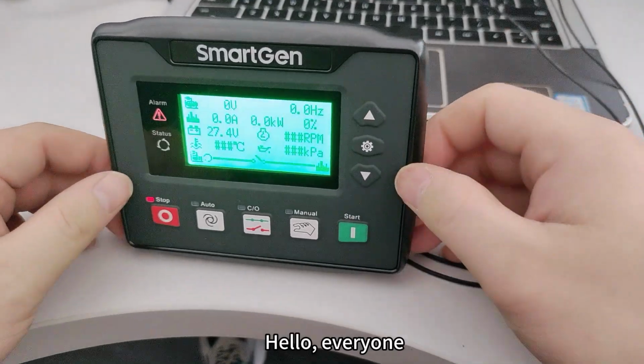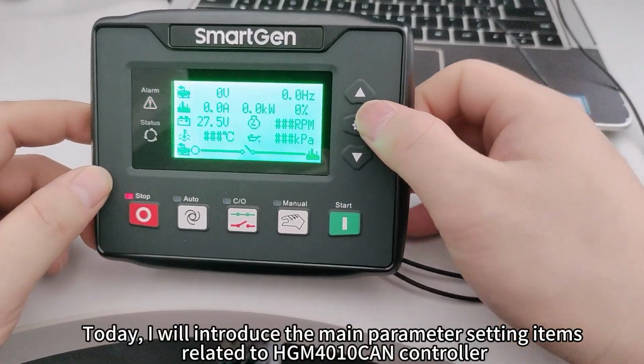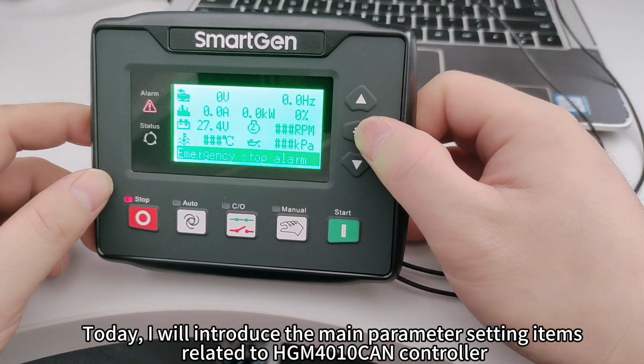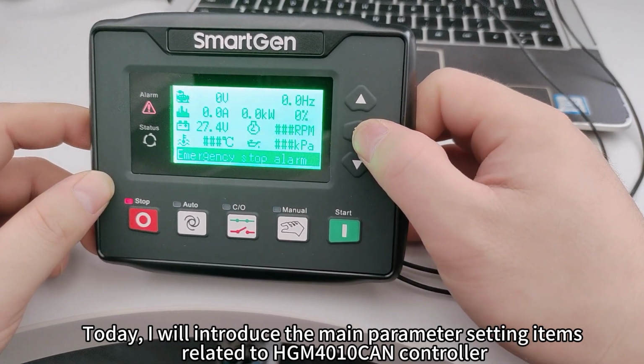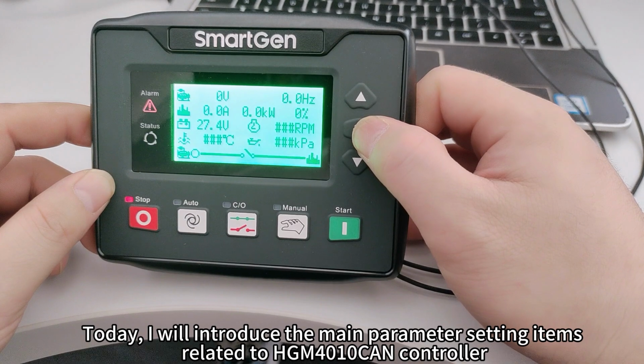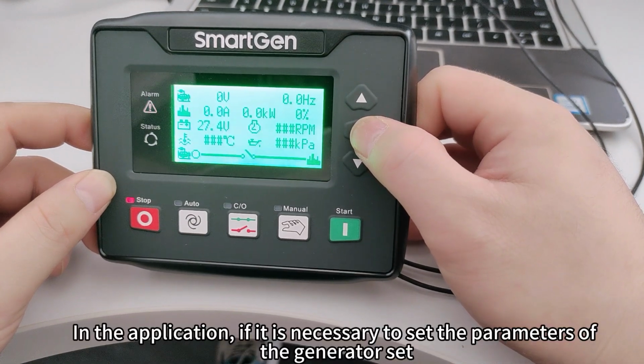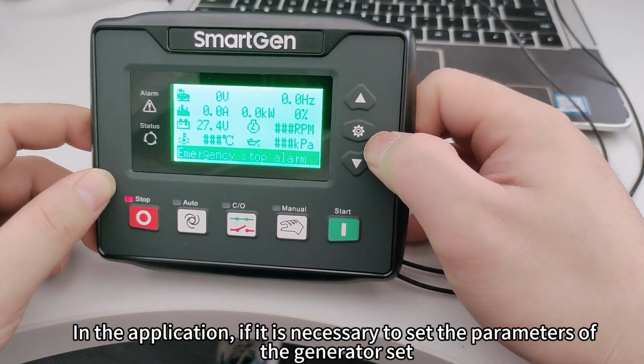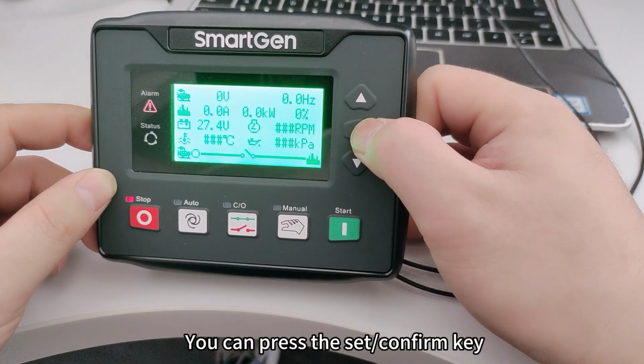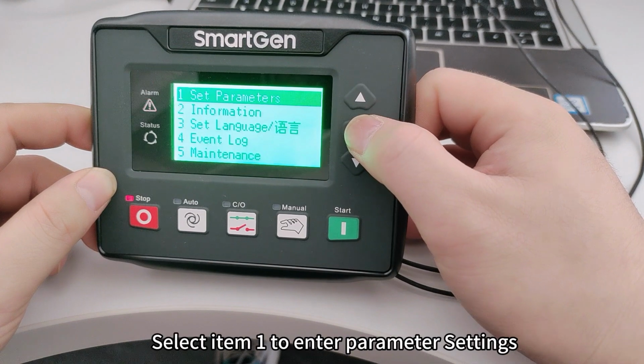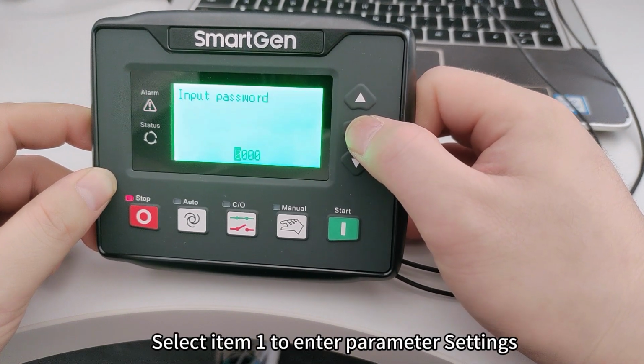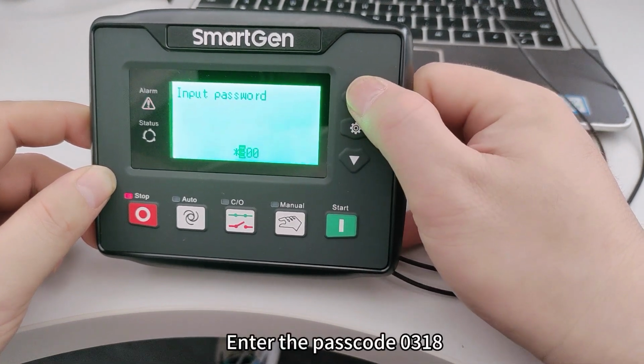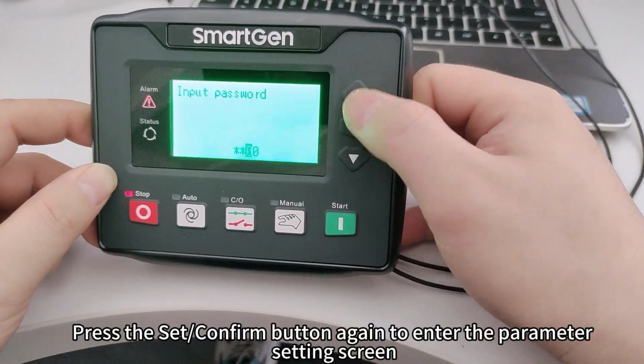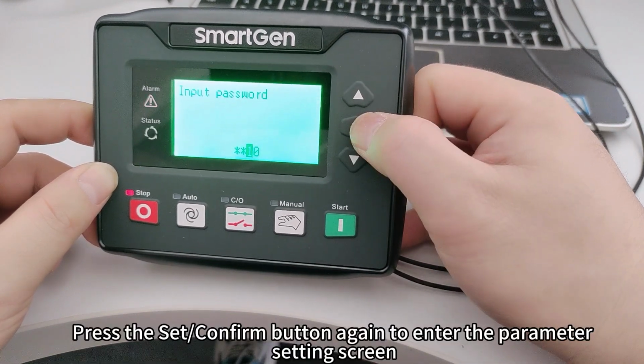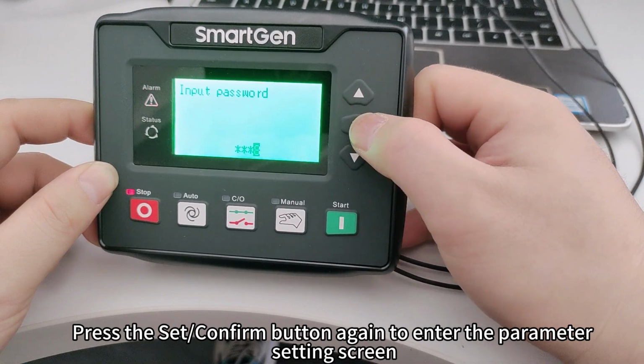Hello, everyone. Today, I will introduce the main parameter setting items related to the HGM4010CAN controller. In the application, if it is necessary to set the parameters of the generator set, you can press the Set Confirm key. Select Item 1 to enter parameter settings. Enter the passcode 0318. Press the Set Confirm button again to enter the parameter settings screen.